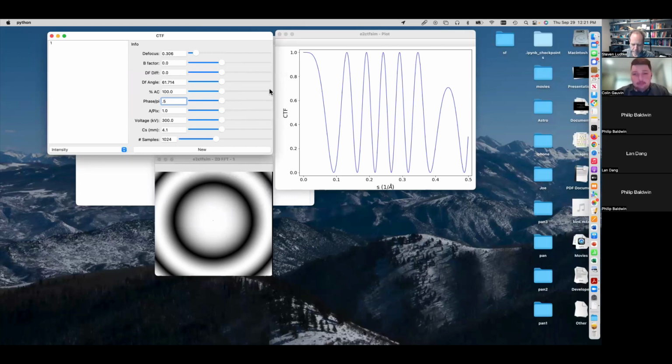So what you're doing is producing a relative phase shift between the unscattered central beam, which is basically at infinitely low resolution, and the rest of the image that comes out. What it does is it sort of produces an artificial amplitude contrast between that unscattered beam and the stuff that gets phase shifted normally by passing through the specimen.